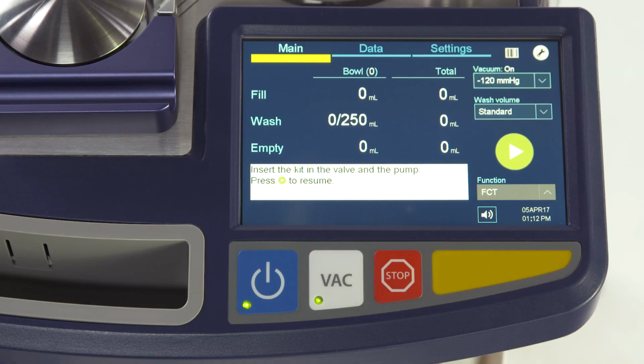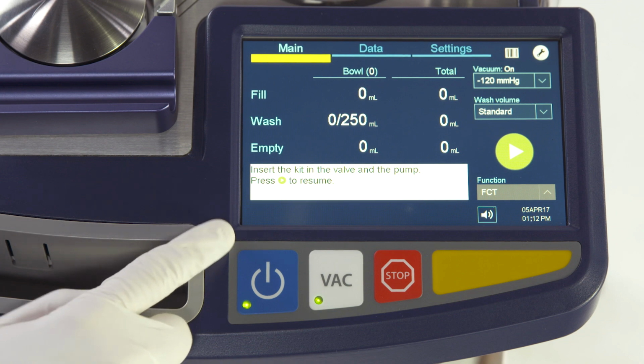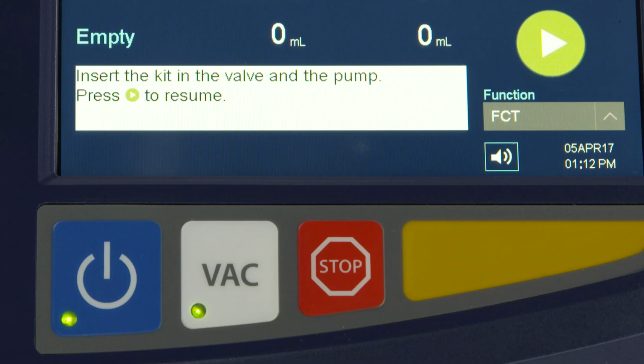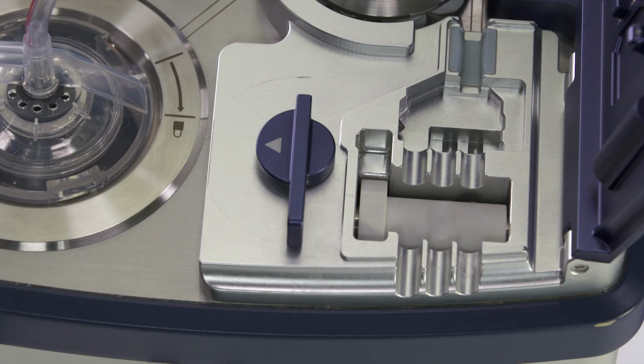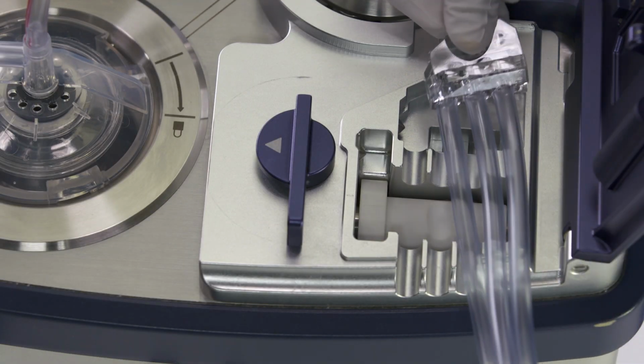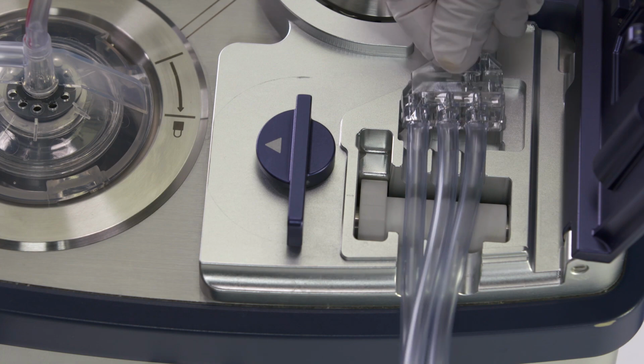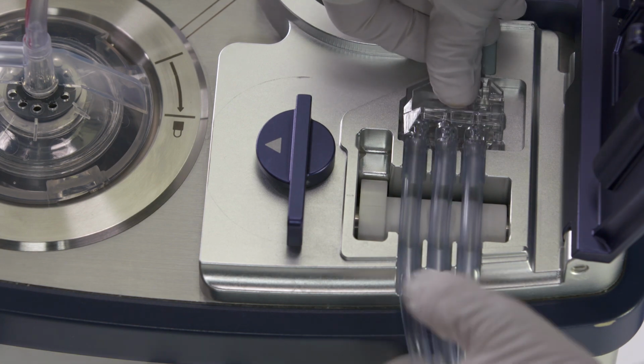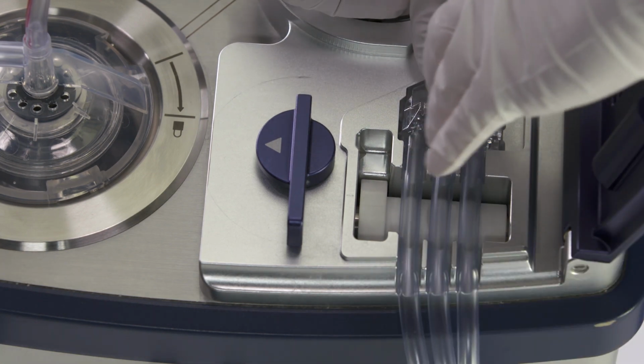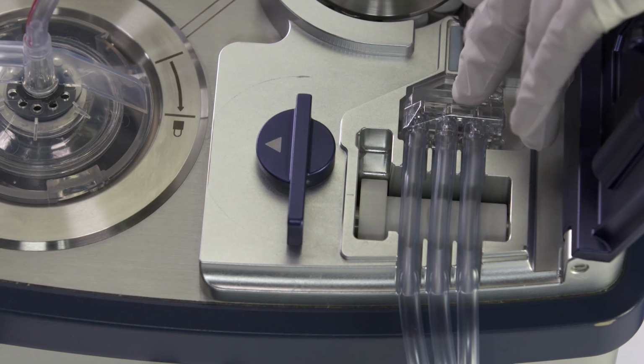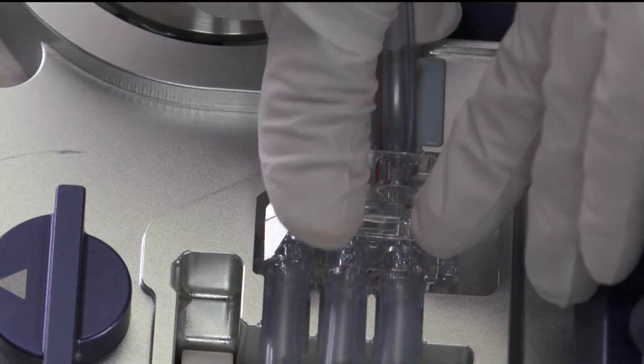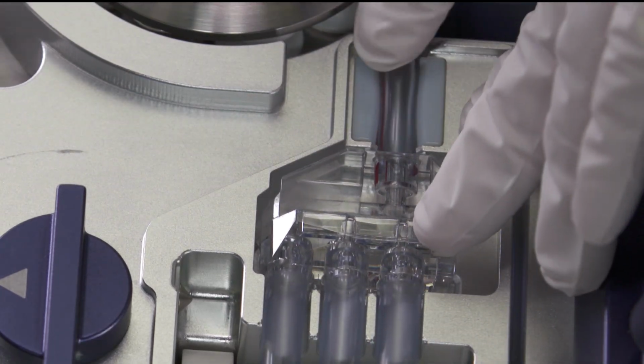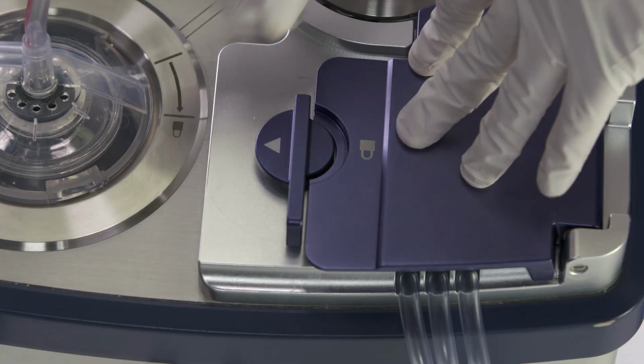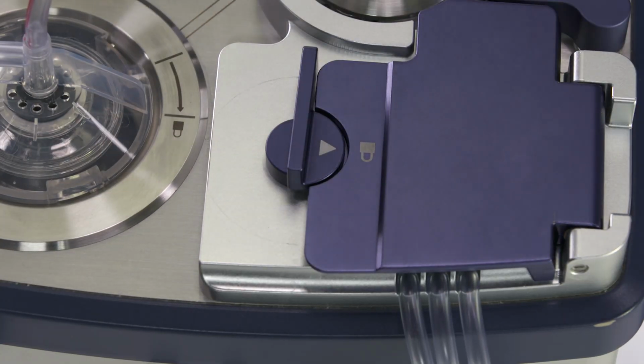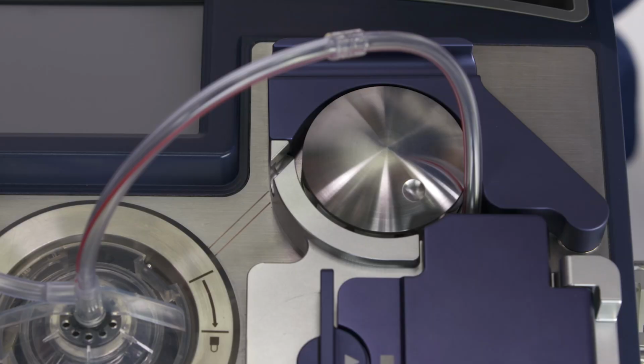At this point, you'll see a message that says, "Insert the kit in the valve and the pump. Press the green button to resume." Place the manifold into the recessed cavity. Place the 3 manifold tubing lines into the tubing guides. Make sure that each of the lines is fully seated in its guide. Next, put the single manifold tubing line into the air detector and close the cover. Then rotate the manifold cover latch until the lock indicators are aligned.